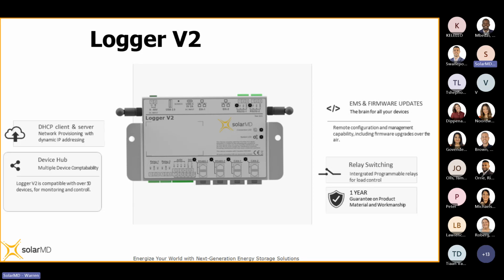But these relays are useful in a number of ways, as most people will end up using the logger to enable a generator with remote start. You can program the logic on the logger so that if the battery reaches a predetermined voltage, say something low like 52 or 51 volts, or a low state of charge, say 20% remaining, the relay must close. This would start your generator that has the remote start function.